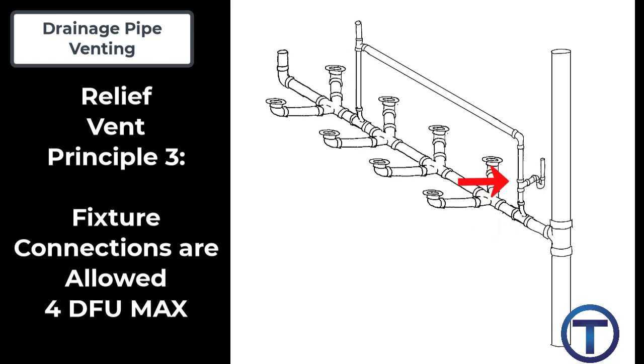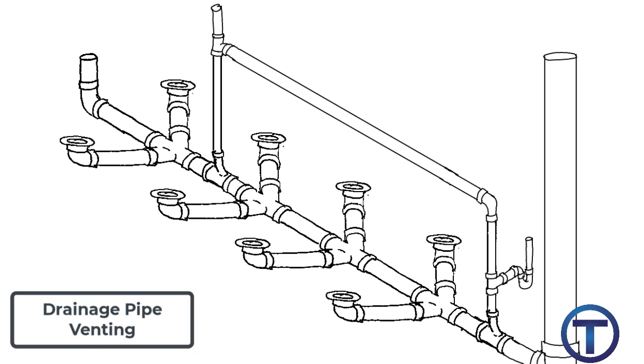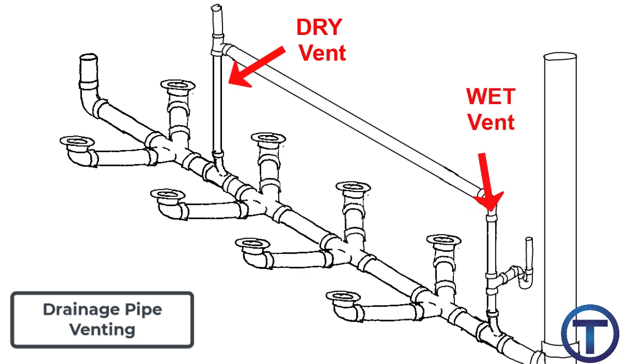Relief vent principle three: the relief vent is allowed to be a fixture drain vent with a maximum of four drainage fixture units. We emphasized earlier that the circuit vent must be a dry vent. But in this case, the relief vent on the downstream side from the circuit can be a wet vent. It could be a sink, a drinking fountain, or anything else, as long as it doesn't exceed four drainage fixture units.